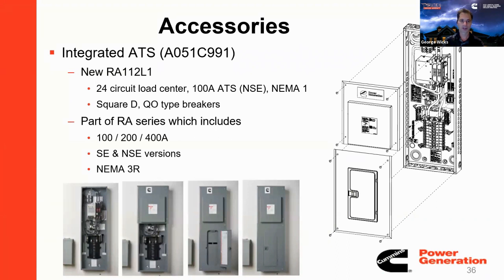So this is just some pictures of the transfer switches. We do have this integrated transfer switch that has breakers built into it for that 400 amp service, using a dedicated circuit setup. So we're not going to do the whole home. We're going to install this 100 amp transfer switch with 24 different bays for breakers that are predetermined coming off the main. So we'll leave back the laundry, the basement, the pool house, and we're just going to run what they consider essential, maybe 10, 15 essential circuits.